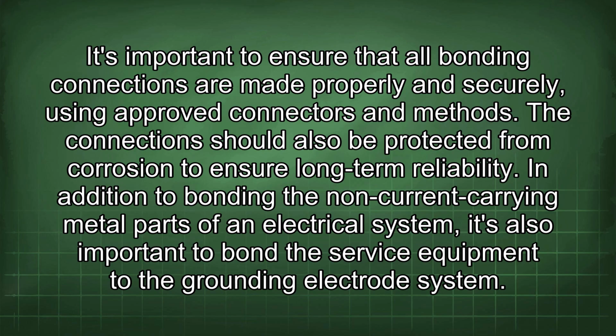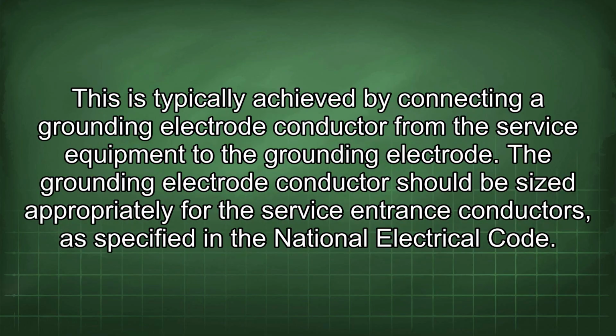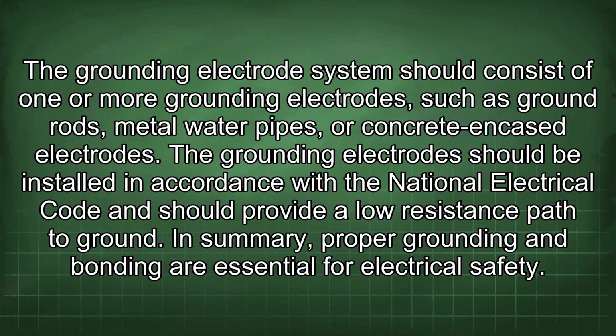In addition to bonding the non-current carrying metal parts of an electrical system, it's also important to bond the service equipment to the grounding electrode system. This is typically achieved by connecting a grounding electrode conductor from the service equipment to the grounding electrode. The grounding electrode conductor should be sized appropriately for the service entrance conductors, as specified in the National Electrical Code. The grounding electrode system should consist of one or more grounding electrodes, such as ground rods, metal water pipes, or concrete encased electrodes. The grounding electrodes should be installed in accordance with the National Electrical Code and should provide a low resistance path to ground.